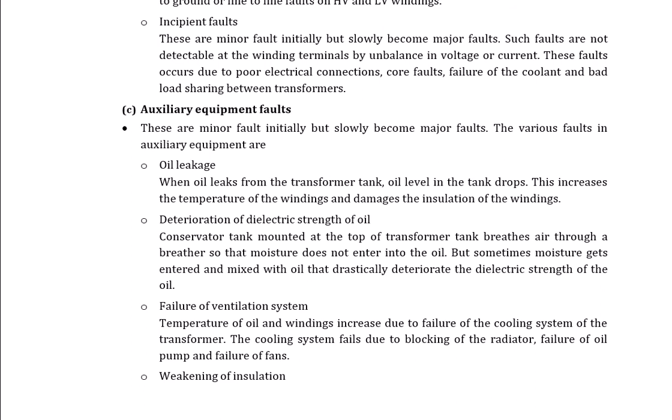Failure of the ventilation system also creates a fault. The temperature of oil and windings increases due to failure of the cooling system of the transformer. The cooling system fails due to blocking of a radiator, failure of the oil pump, and failure of fans. And also sometimes weakening of insulation creates a fault.